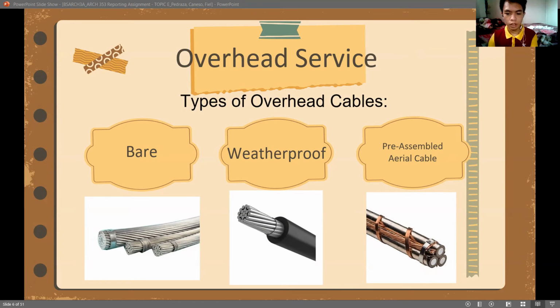Here are the types of overhead cables. Overhead cables are of several types: bare, weatherproof, pre-assembled aerial cable. Bare copper cable supported on porcelain or glass insulators on cross arms is normally used for high voltage, 2.4 kilovolts and higher lines. Secondary circuits at 600 volts and below are generally run on porcelain spool secondary racks with weatherproof cable as the conductor.